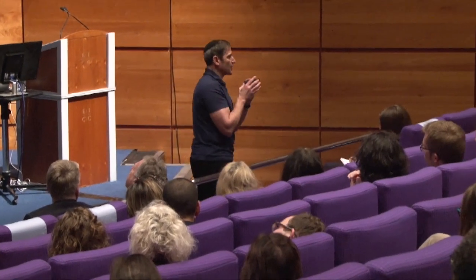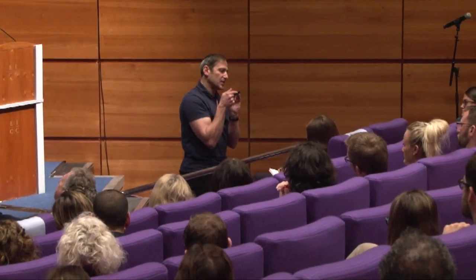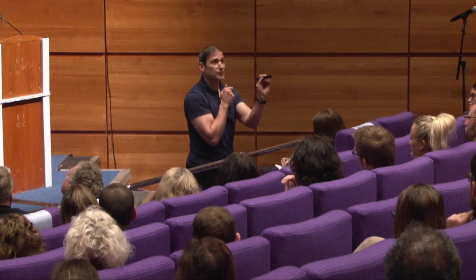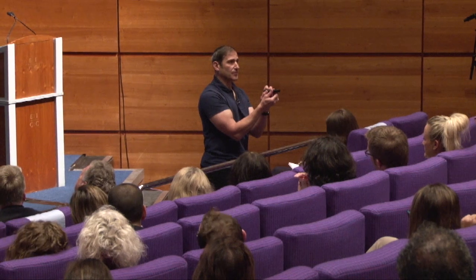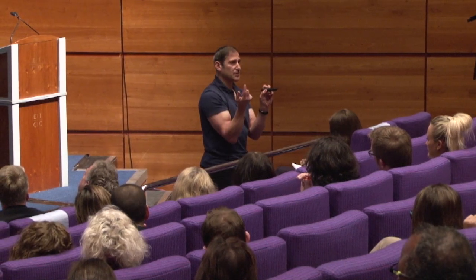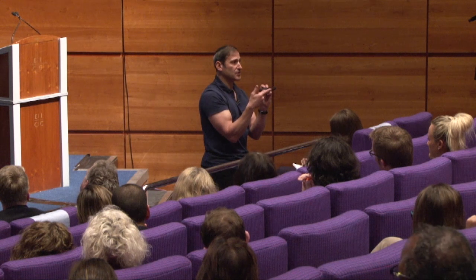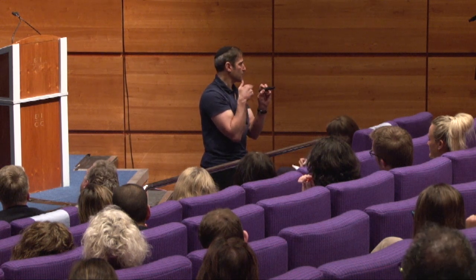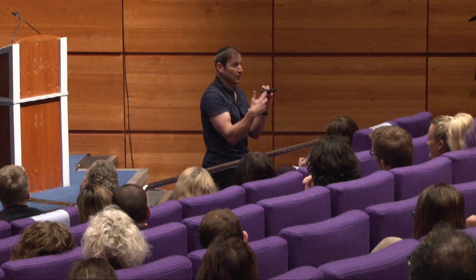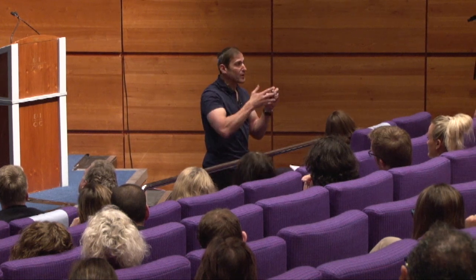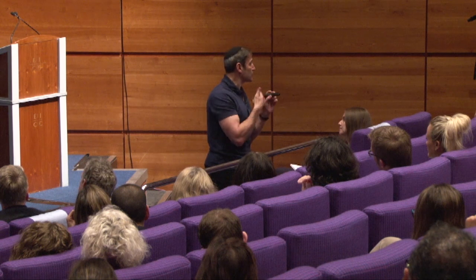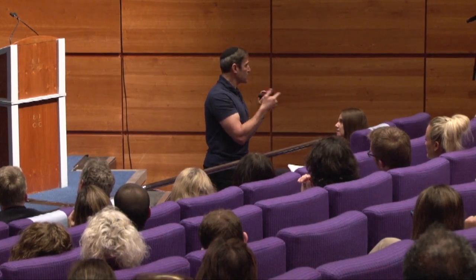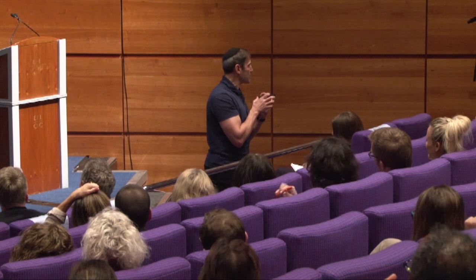3 Tesla, 1 Tesla. What attracts it to go that way is that if I'm walking into the MR scanner room, and over here there's a certain field, and over here the field is less, it will translate, it will move, it will feel a displacement force in the direction of the greater field. If everything here is completely homogeneous, there is 0 difference across the wrench from here to here, and so there's no displacement force, that way, this way, that way. Oh, there's gravity, so then it'll respond to that force. But from a magnetic point of view, there's no translational force because there's 0 delta, there's 0 difference across it.